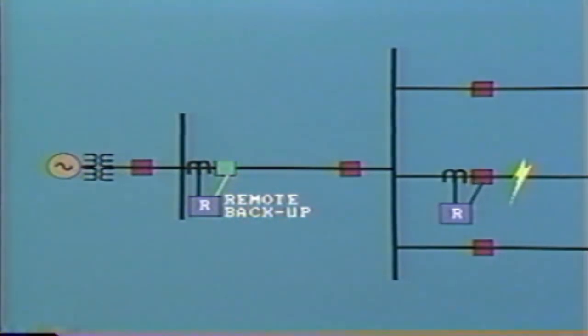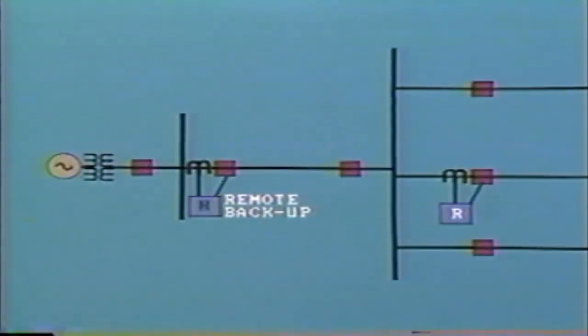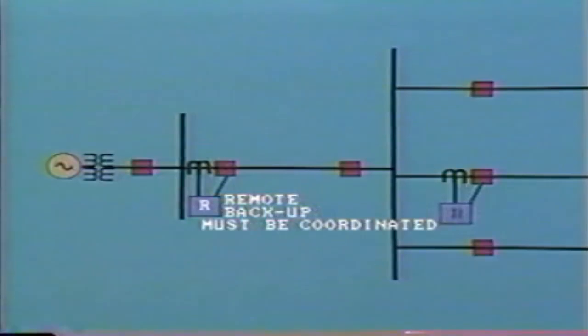When remote backup relays operate, they will generally isolate a larger area from the system and so cause a loss of power supply to more customers. The backup relays must be correctly coordinated so that they allow primary protective schemes to operate first. Only in the case of failure of the primary protection would the backup relays need to operate. We'll be looking at all of this in great detail as we proceed through this program. Remember, at this point, we're looking only at the basic philosophies behind protective schemes.